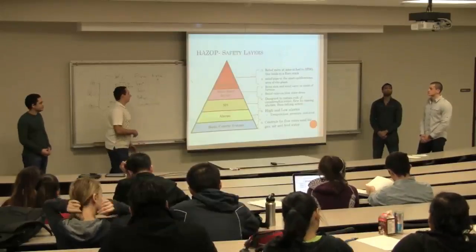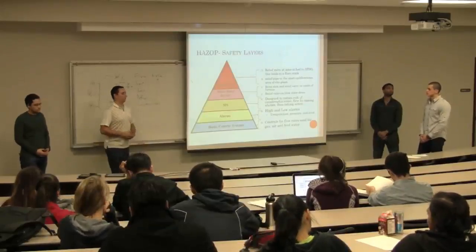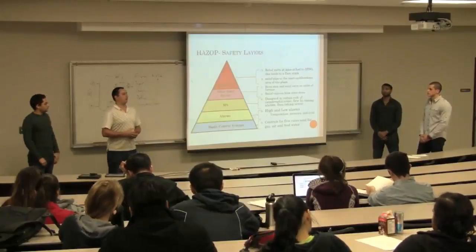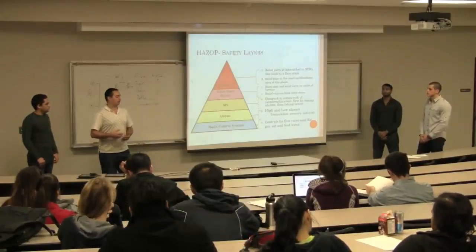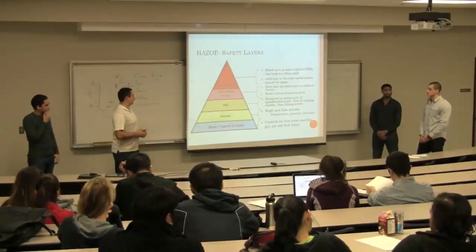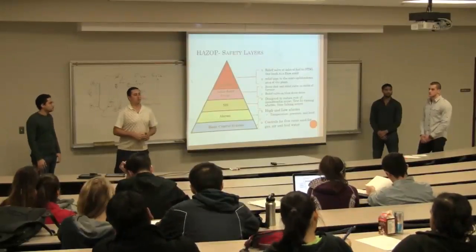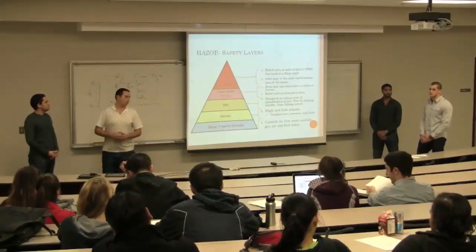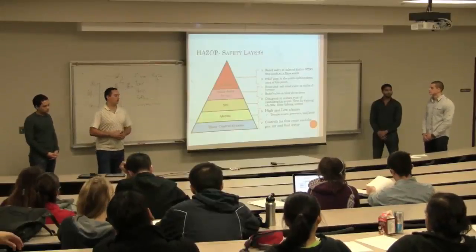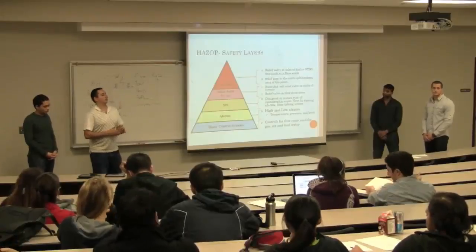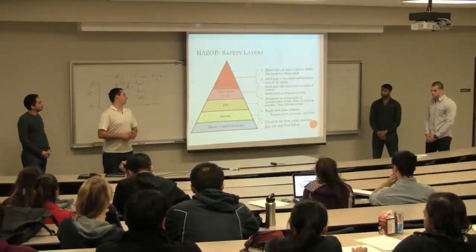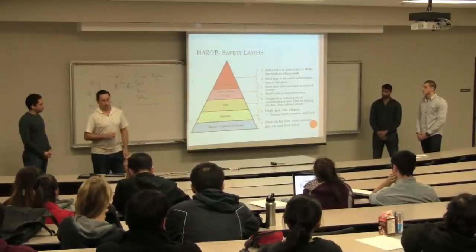So from the bottom towards the top, you start with your basic control systems, and those included flow controls, valve controls to control the flow or pressure. Along with that, there were also some controls designed on pumps to control the speeds of the pumps. Next, we installed high and low alarms. These were for pressure and temperature, and level alarms as well, installed on the OTSG unit.